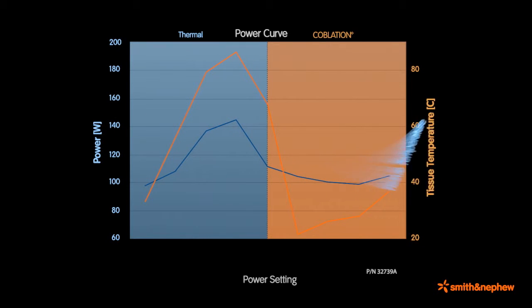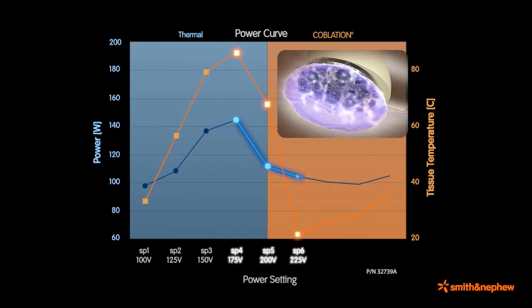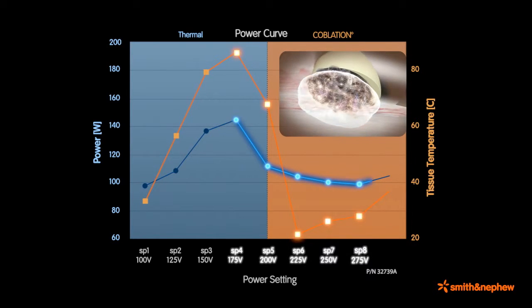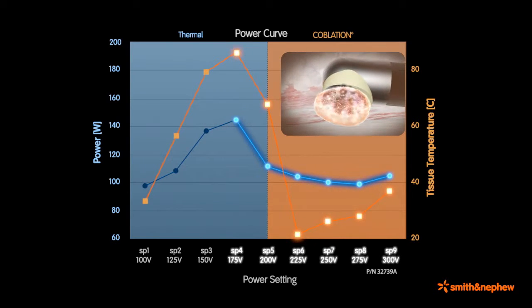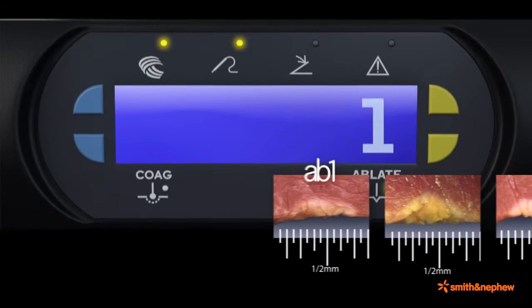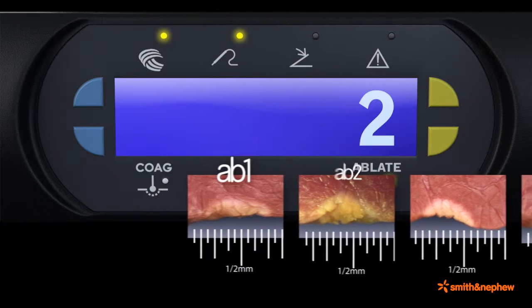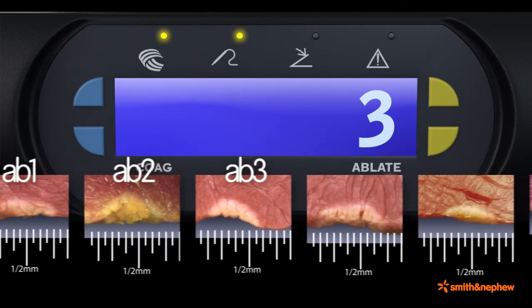While operating in the ablation mode, the transition and intensity of plasma can be best illustrated using a power curve, showing outputs associated with each controller setting. The accompanying images demonstrate how the tissue effects change with each increasing controller setting using the SuperTurboVac device.